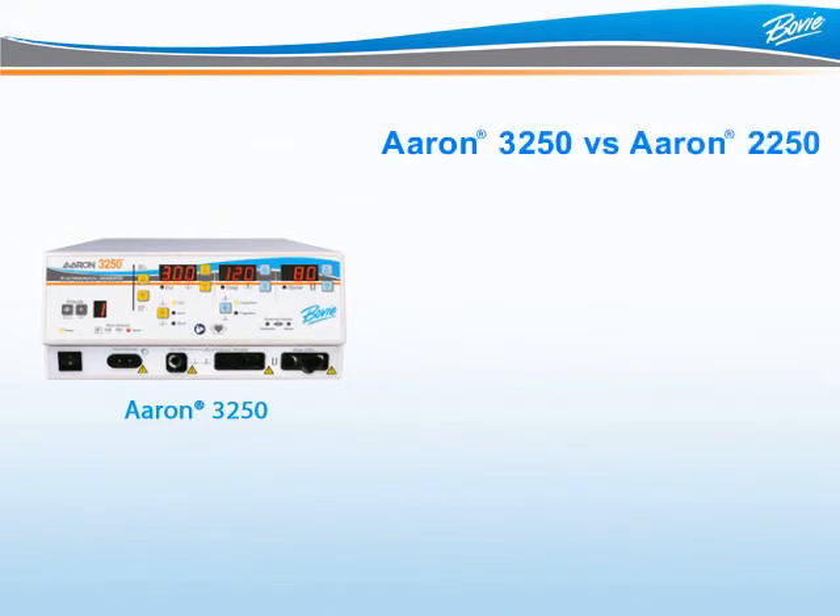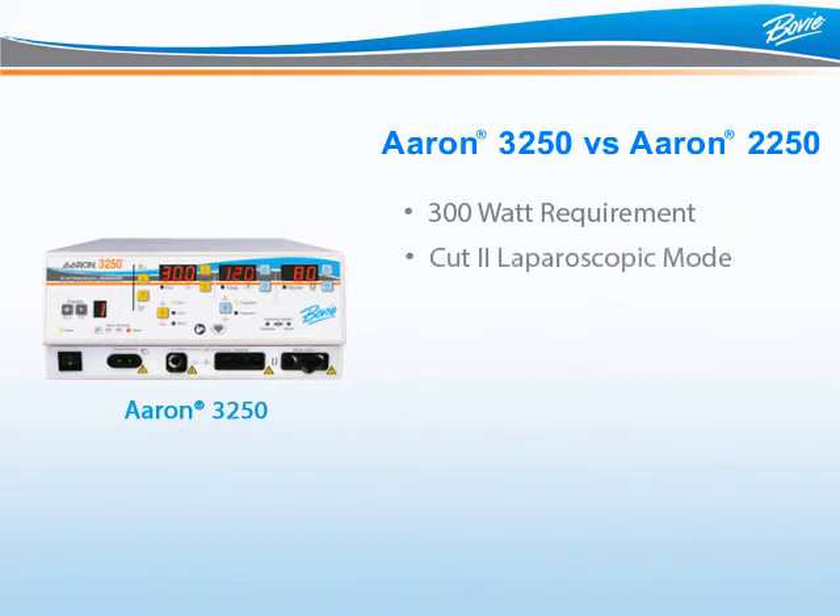The Aaron 3250 and the Aaron 2250 have many of the same features and benefits, so how does one know when it is appropriate to move up to the Aaron 3250? First, is there a 300-watt requirement? Many hospital operating rooms require a minimum of 300 watts of available power in their specifications — for this, the Aaron 3250 is the obvious choice. Second, any facility performing laparoscopic or microsurgery procedures will benefit from the additional safety provided by the Cut 2 mode, which is only available on the Aaron 3250. Third, the Aaron 3250 provides 10 automatic presets for quick transition between procedures. Fourth, the Aaron 3250 is priced significantly lower than most OR generators and is capable of the vast majority of OR procedures.